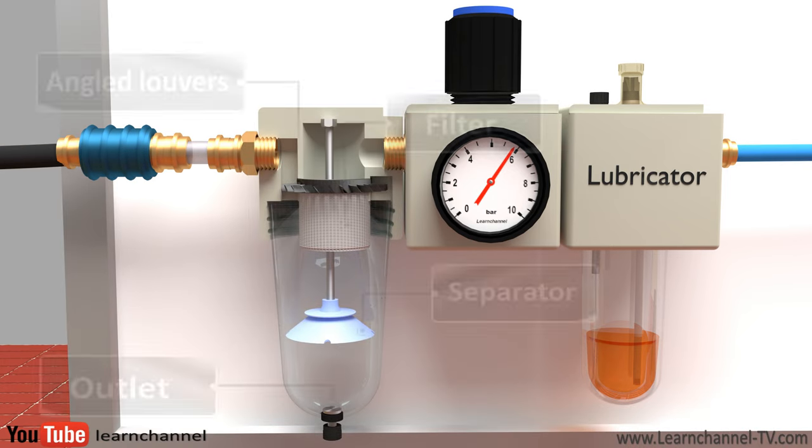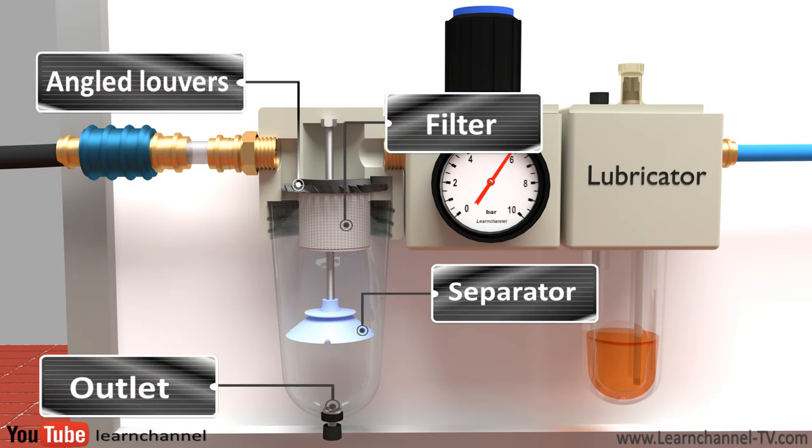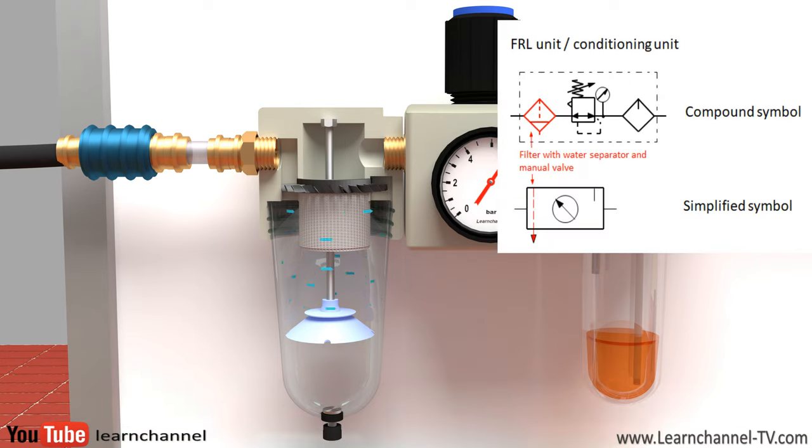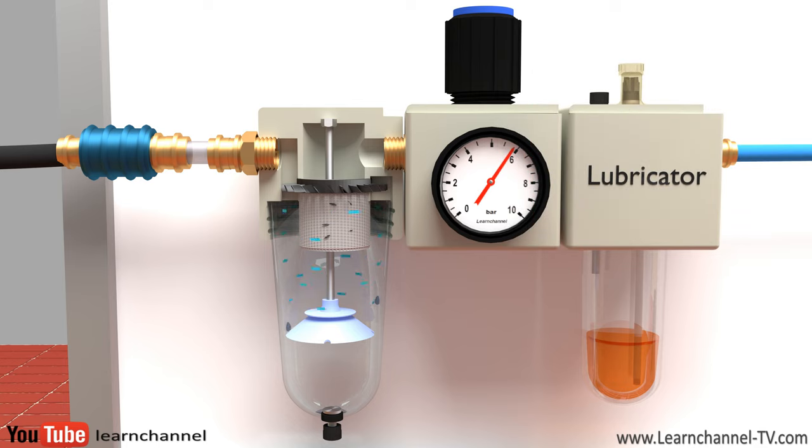Air enters the air filter through angled louvers. This causes the air to spin as it enters the bowl. Due to the centrifugal force of the rotating air, the larger particles of dirt, rust, and water are thrown against the inner wall of the filter bowl. These contaminants then flow down to the bottom of the filter bowl. The separator disc divides the filter into a zone with air circulating and a slowdown zone. This way, the condensate cannot be picked up by the air flow again.